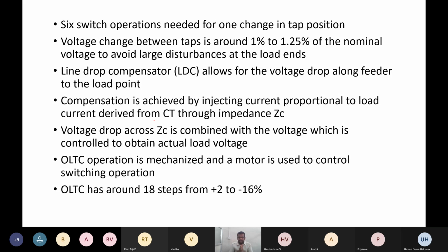First we have to measure the current and measure the voltage drops, and combine the voltage drops that we witnessed at the load side and also at ZC. Combine those voltages in order to control the actual load voltage, and inject the required amount of lagging current or leading current. By injecting the leading or lagging current, we can balance the leading or lagging component of the circuit. Because of this balancing, we can control the voltage. And by controlling the voltage through lagging or leading current, we can control the reactive power. That's the concept.